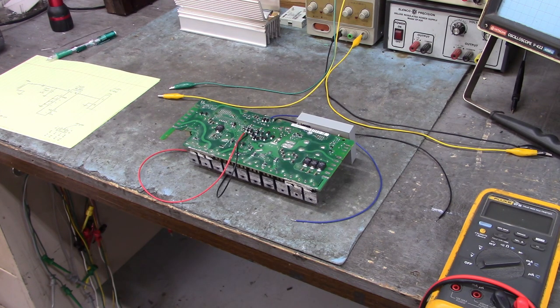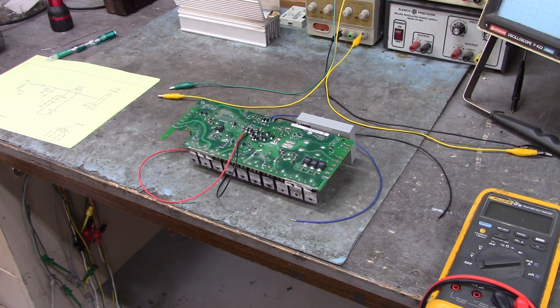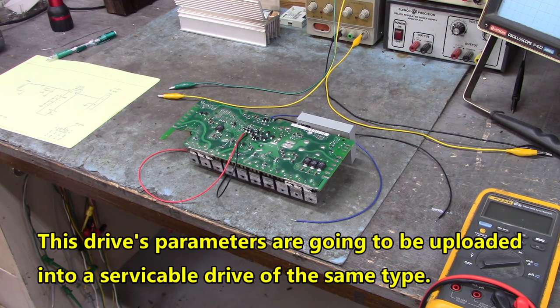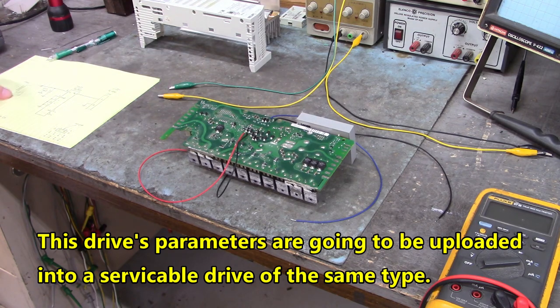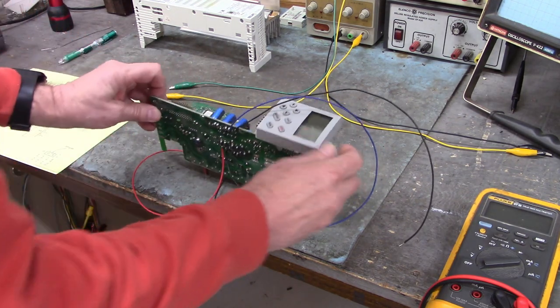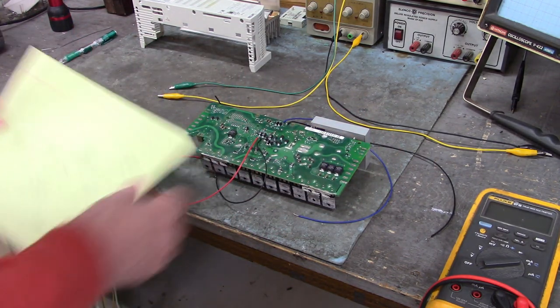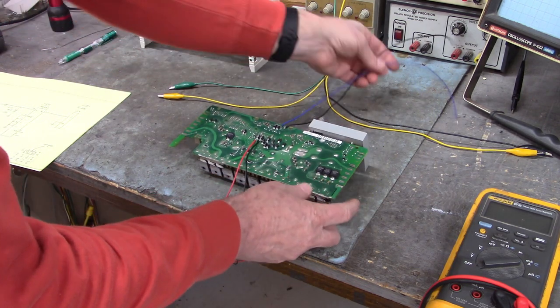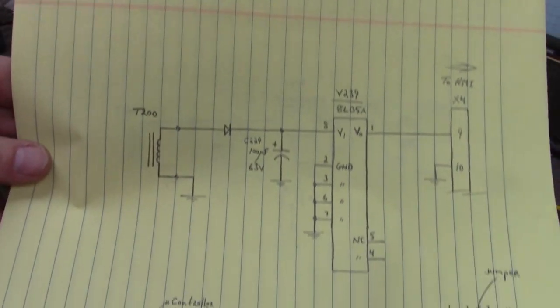Good morning. Here we have a Lenze inverter drive type E82EV152S4B and it has a shorted three-phase bridge rectifier input. I want to pull the parameters out of it and I can't power it up with that shorted three-phase bridge rectifier. So what I did was I mapped out the power supply section for the HMI panel, the human interface panel right here. There's a power supply that powers it up and there's also another power supply that powers up the control board right here. I've tacked wires across the relevant capacitors to power up those two separate sections.